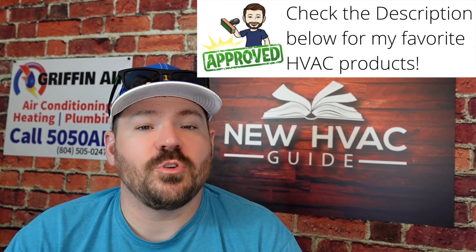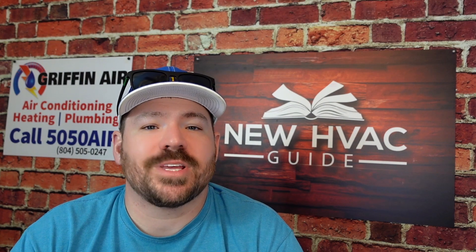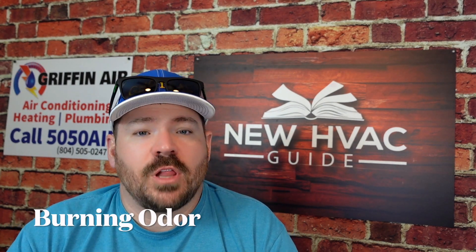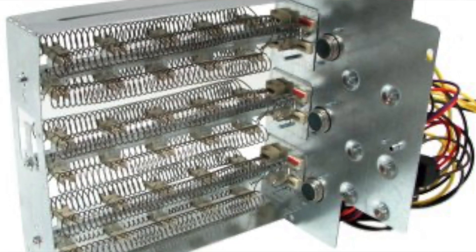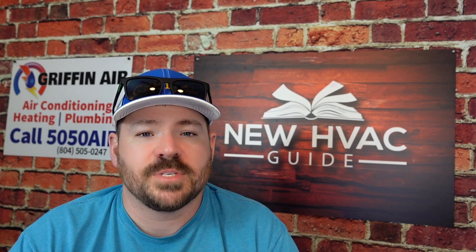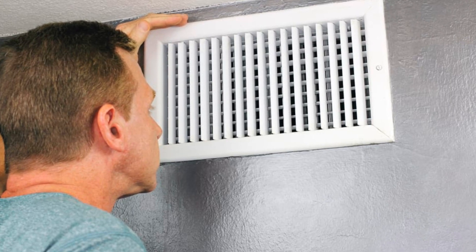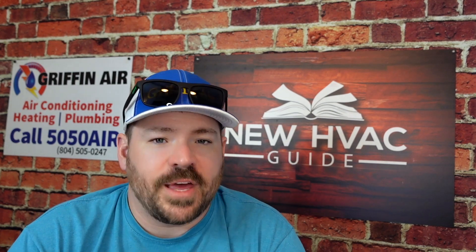Number six: be aware that if you have some sort of elements or heat kit in that system — a lot of heat pump systems will have backup electric heat — there will be a burning odor. Many homeowners not used to that type of system will think something is super wrong when they smell it. What's burning is the dust that has collected on those heat strips. I tell most folks to go ahead and turn the emergency heat on now so that when you smell that odor you know exactly what it is and it's not scaring you in the future.